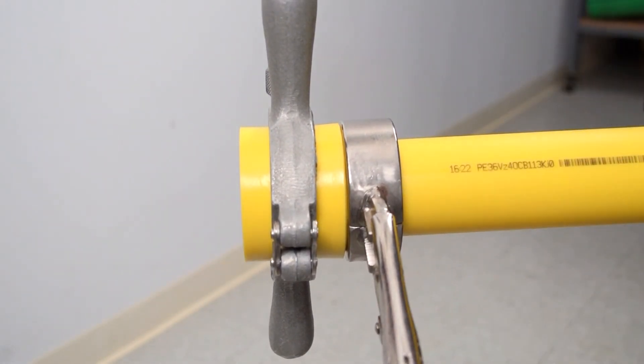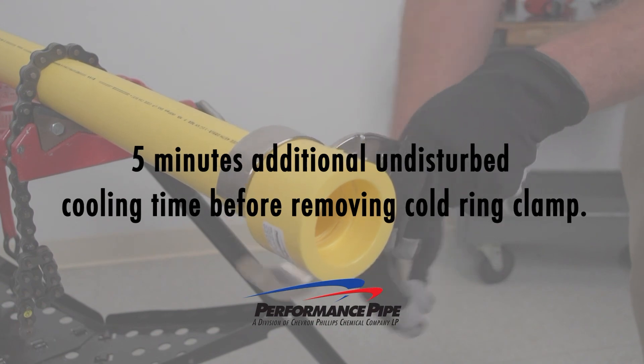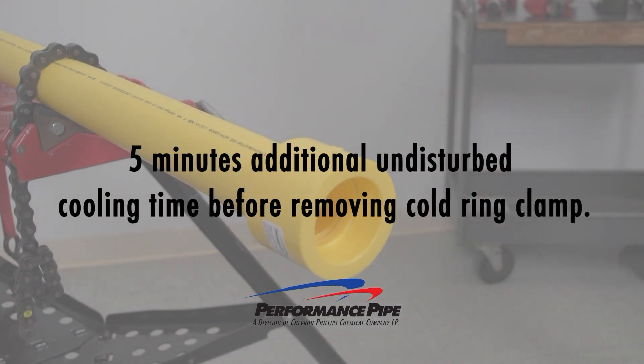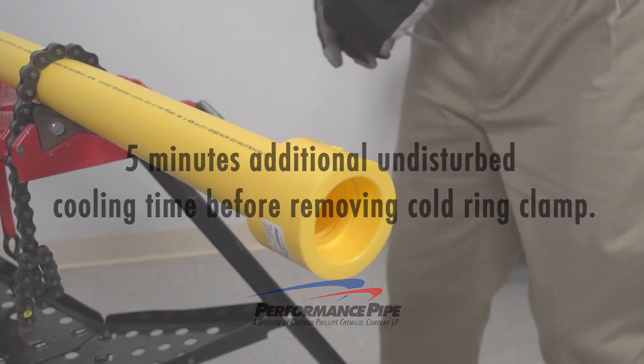Holding force may be relaxed when the cooling time ends. After an additional undisturbed cooling time, the cold ring clamp may be removed. Then, testing, burial, or fusing the other end of the fitting can be performed.